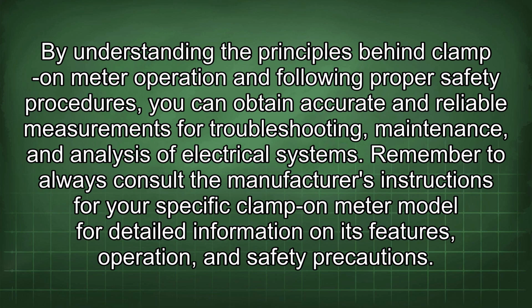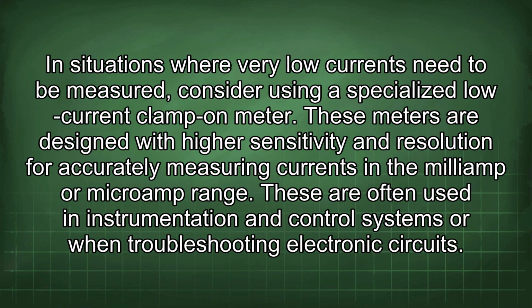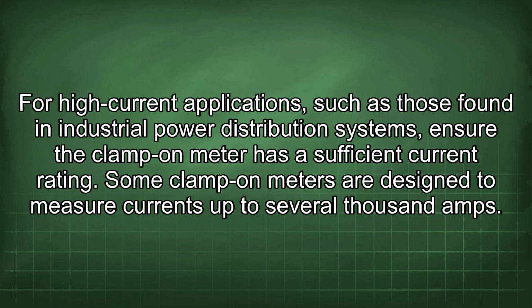In situations where very low currents need to be measured, consider using a specialized low-current clamp-on meter. These meters are designed with higher sensitivity and resolution for accurately measuring currents in the milliamp or microamp range. These are often used in instrumentation and control systems or when troubleshooting electronic circuits. For high current applications, such as those found in industrial power distribution systems, ensure the clamp-on meter has a sufficient current rating. Some clamp-on meters are designed to measure currents up to several thousand amps.